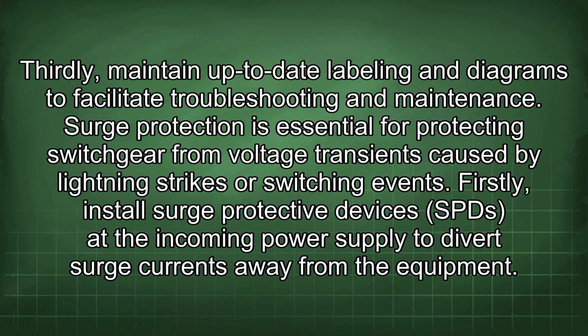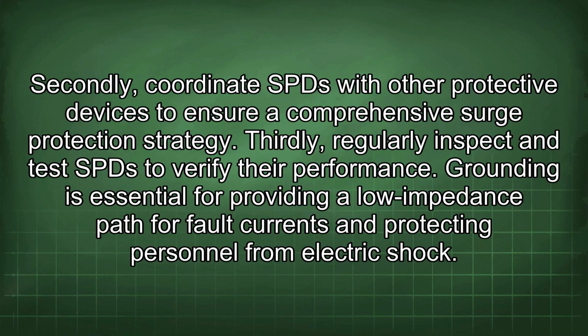Surge protection is essential for protecting switchgear from voltage transients caused by lightning strikes or switching events. Firstly, install surge protective devices (SPD) at the incoming power supply to divert surge currents away from the equipment. Secondly, coordinate SPD with other protective devices to ensure a comprehensive surge protection strategy. Thirdly, regularly inspect and test SPD to verify their performance.